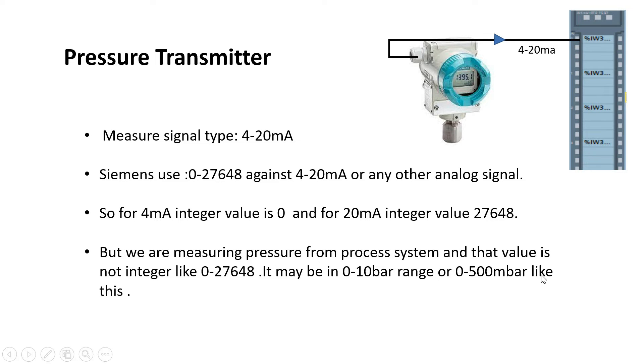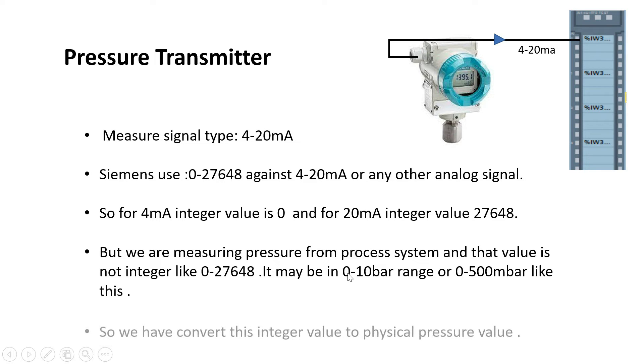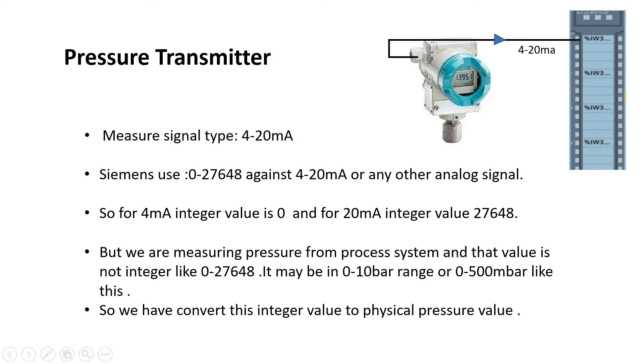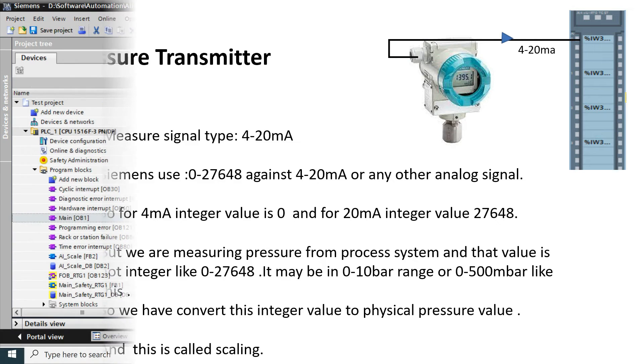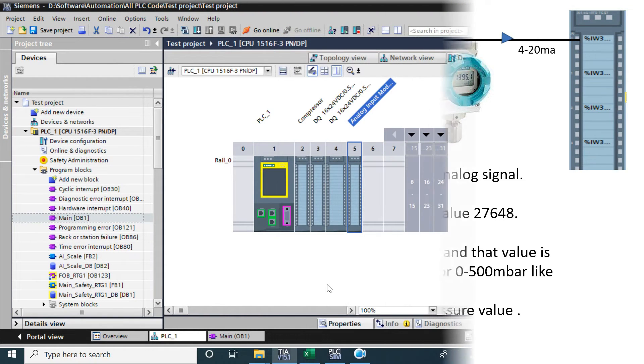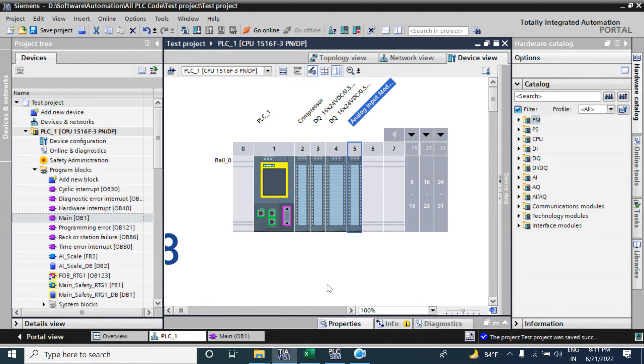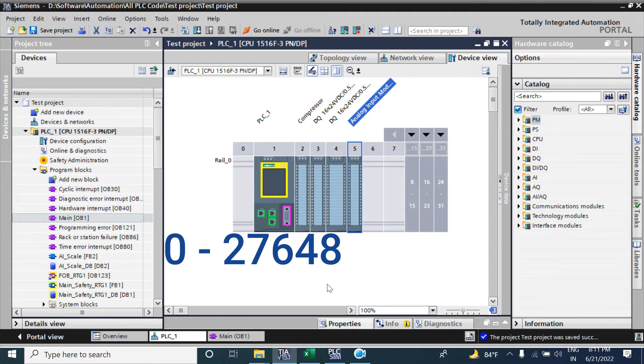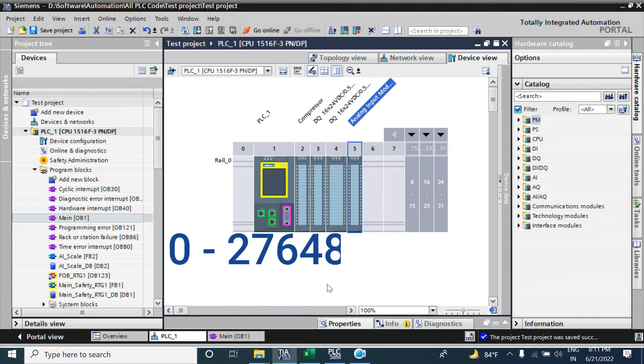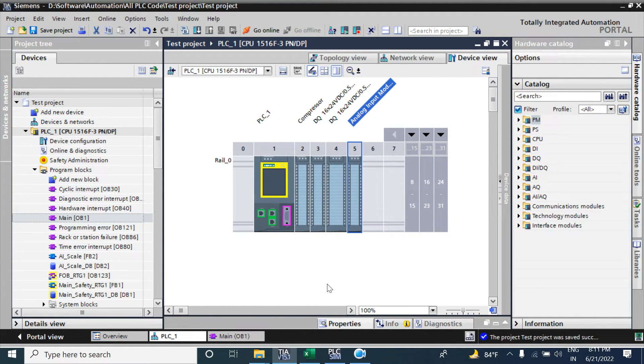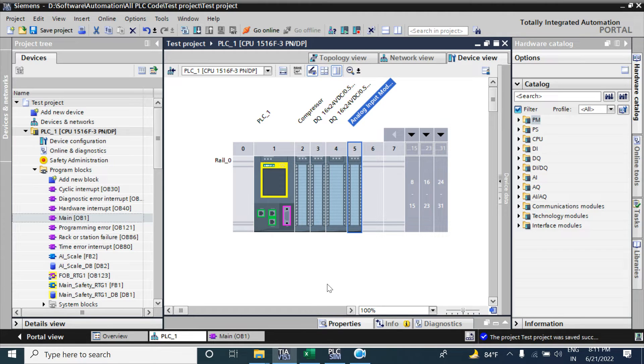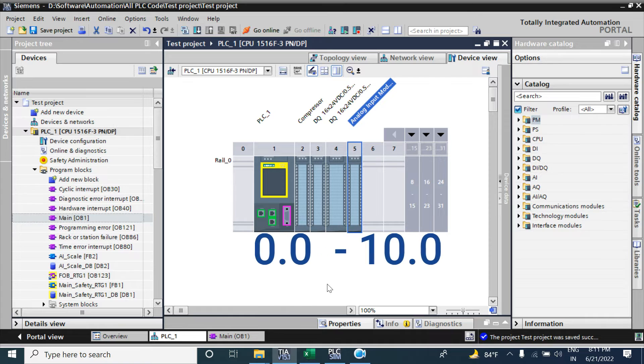So we have to convert this integer value to the physical pressure range, and this is called scaling. Now we will convert this integer value 0 to 27648 into our desired pressure range. If the pressure transmitter range is 0 to 10 bar, then we will convert it into 0 to 10 bar.